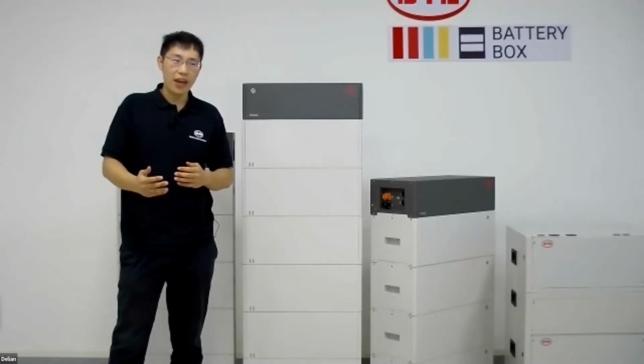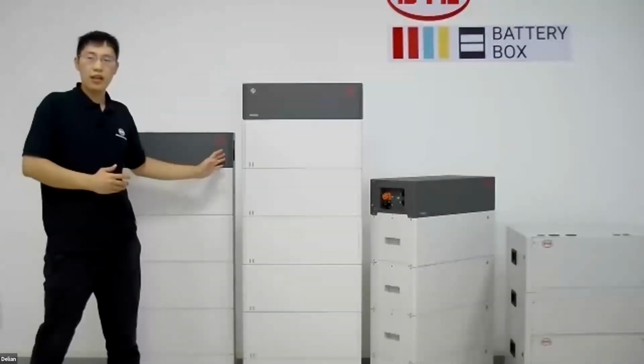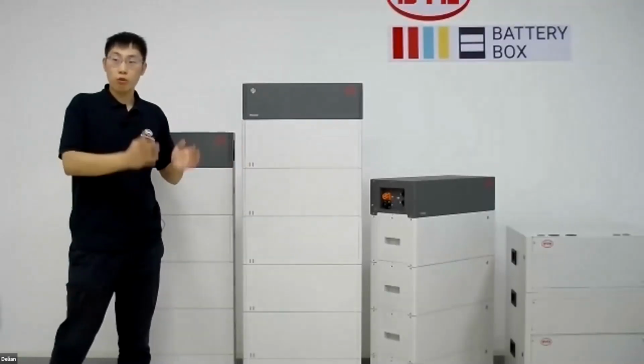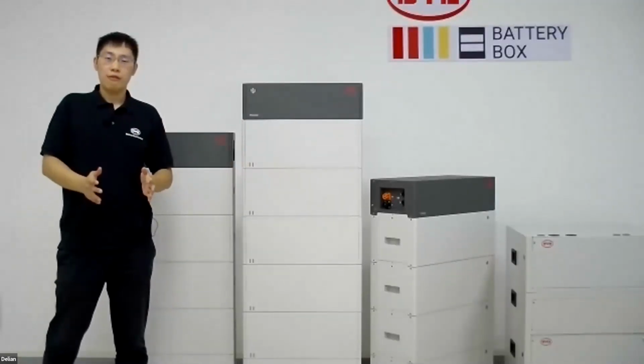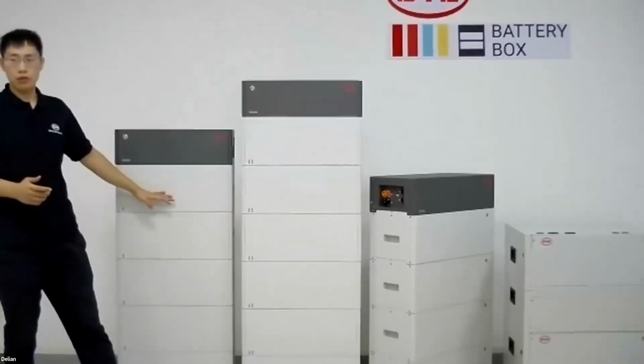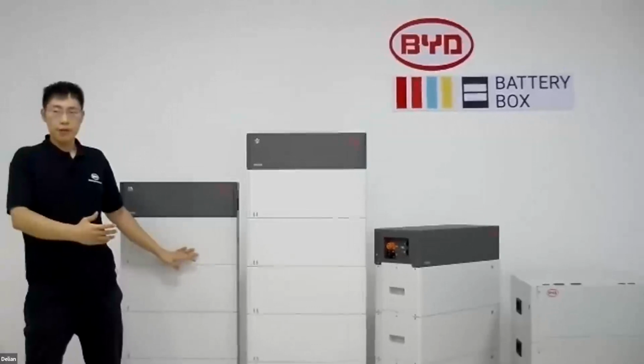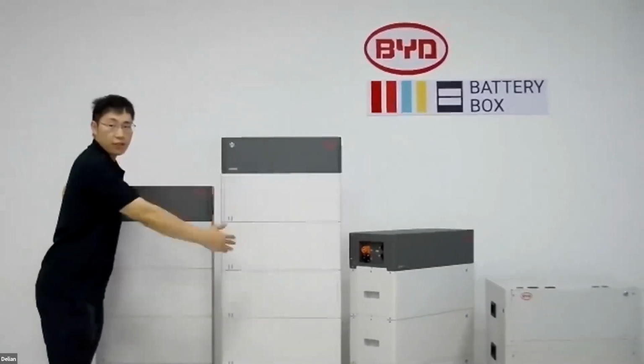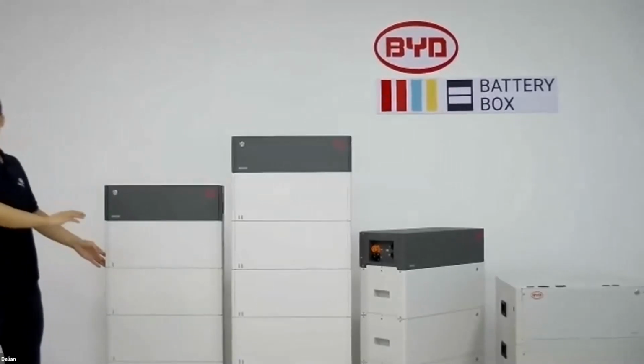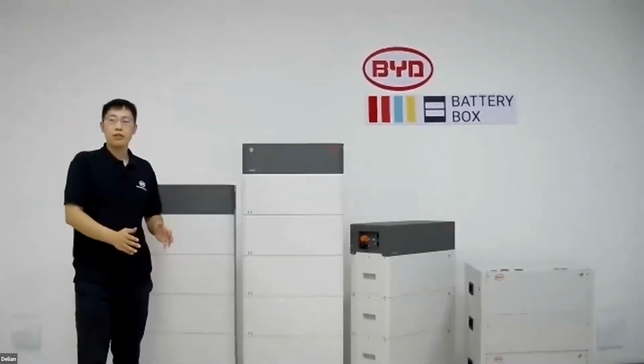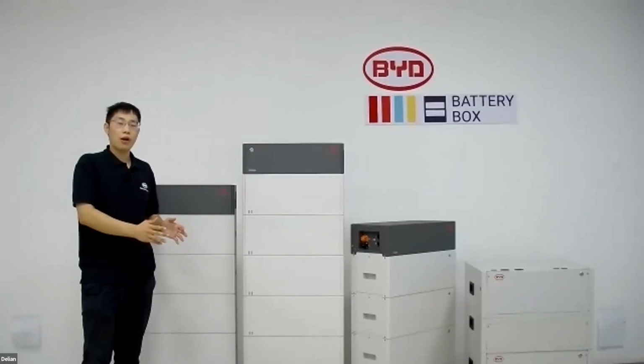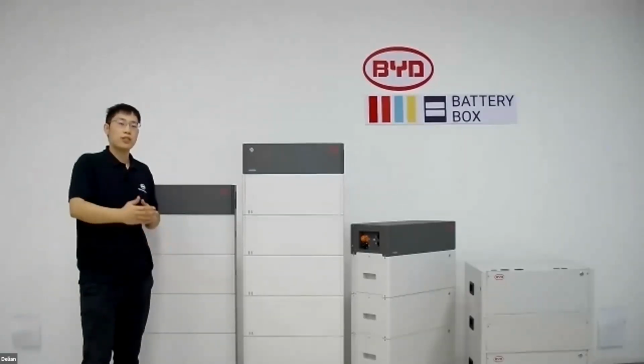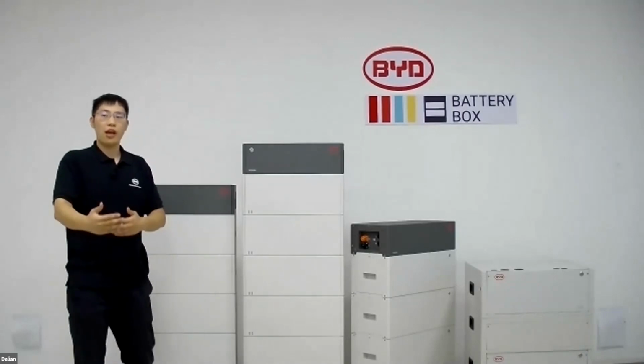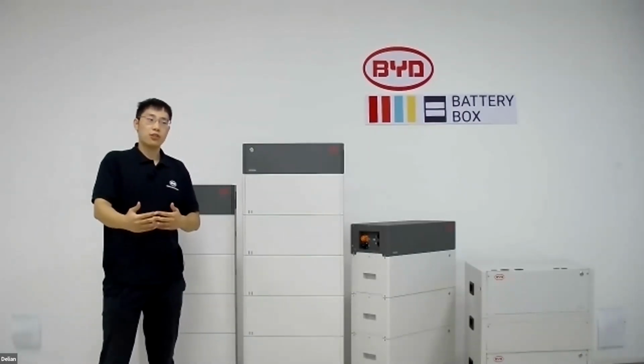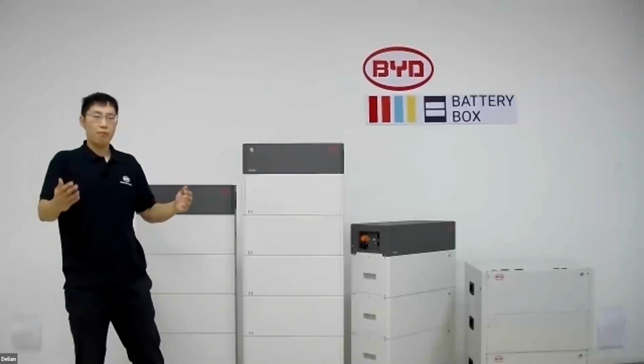As I mentioned, for both HVS and HVM versions, we support up to 3 stacks in parallel. For example, if you've got HVS models and the capacity is not enough, you can have up to 3 stacks in parallel. But for high voltage, always make sure that when you parallel the systems, each stack, each tower, has to have the same modules to keep the same voltage. Because if you parallel, you've got to have the same voltage, otherwise it's not going to work.